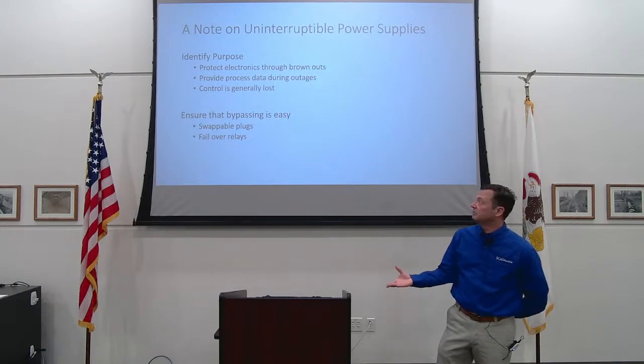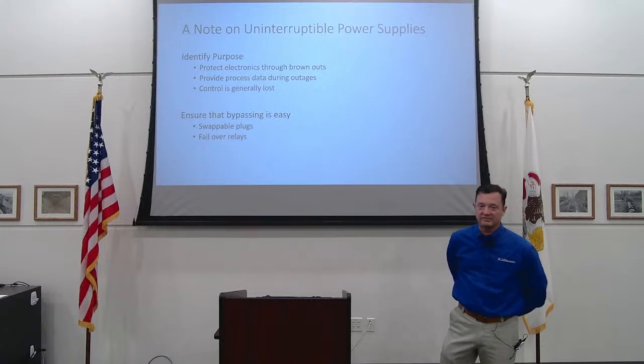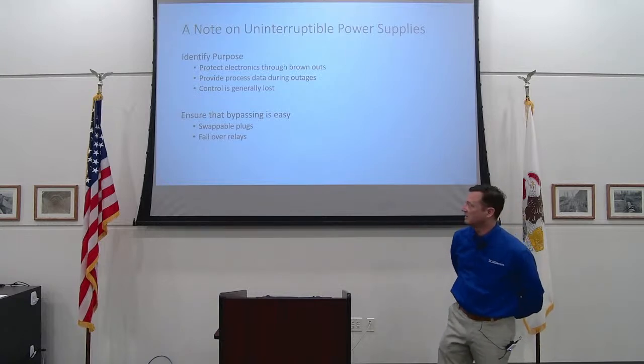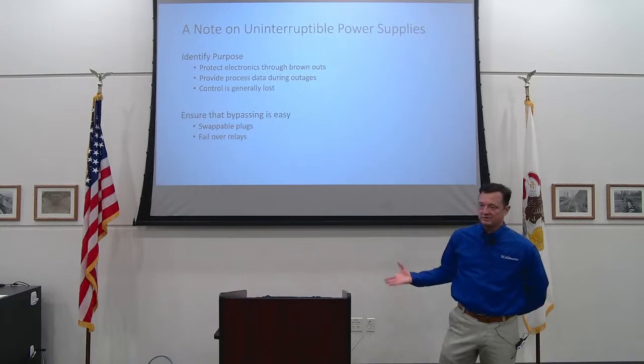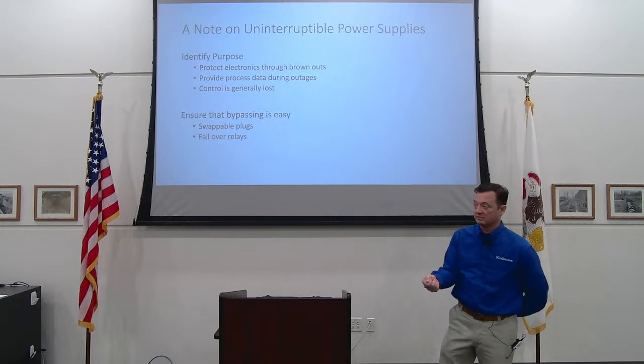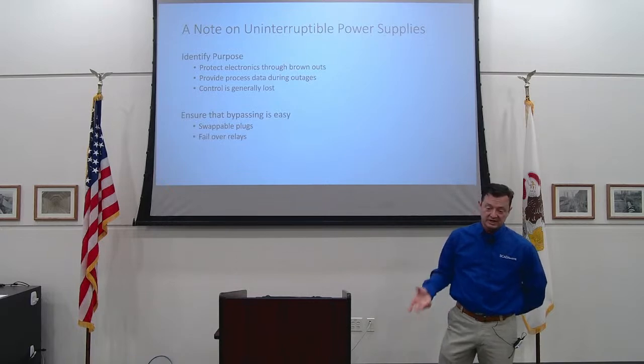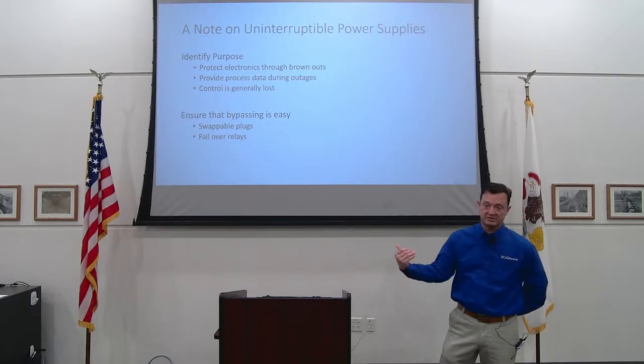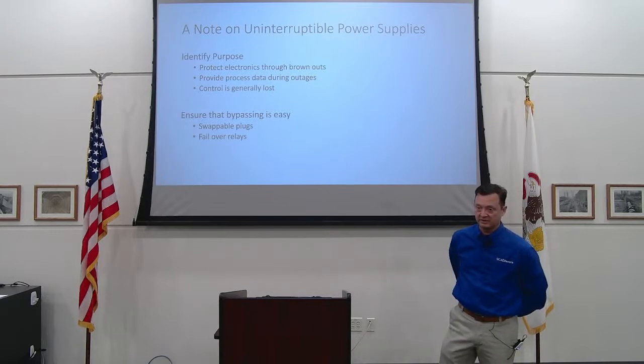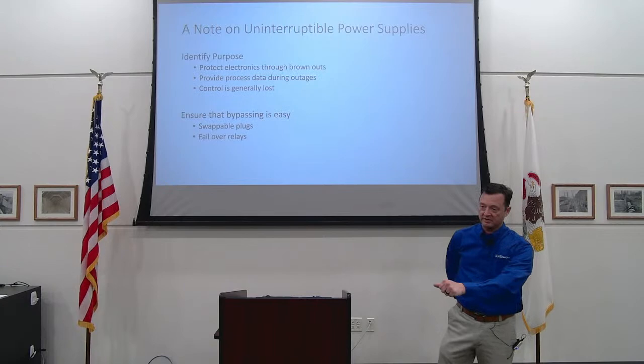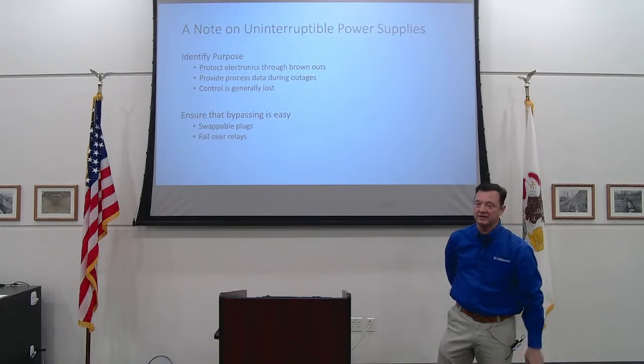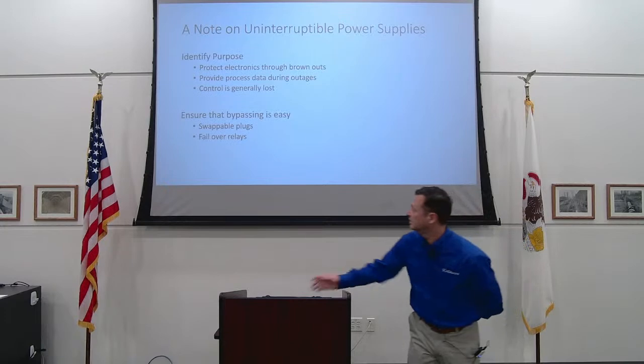Because they fail so much, it's important that they're easy to swap. So like I said before, make sure that the UPSs on your control stuff have swappable plugs. What we've actually started to do in some of our newer control systems is install a relay in the panel so that if the UPS power fails and the line power is still on, it automatically bypasses the UPS and then lets you know. In the ones that we've installed, you can hit the power off on the UPS and you don't lose power to anything inside the cabinet. It just switches over to line power.